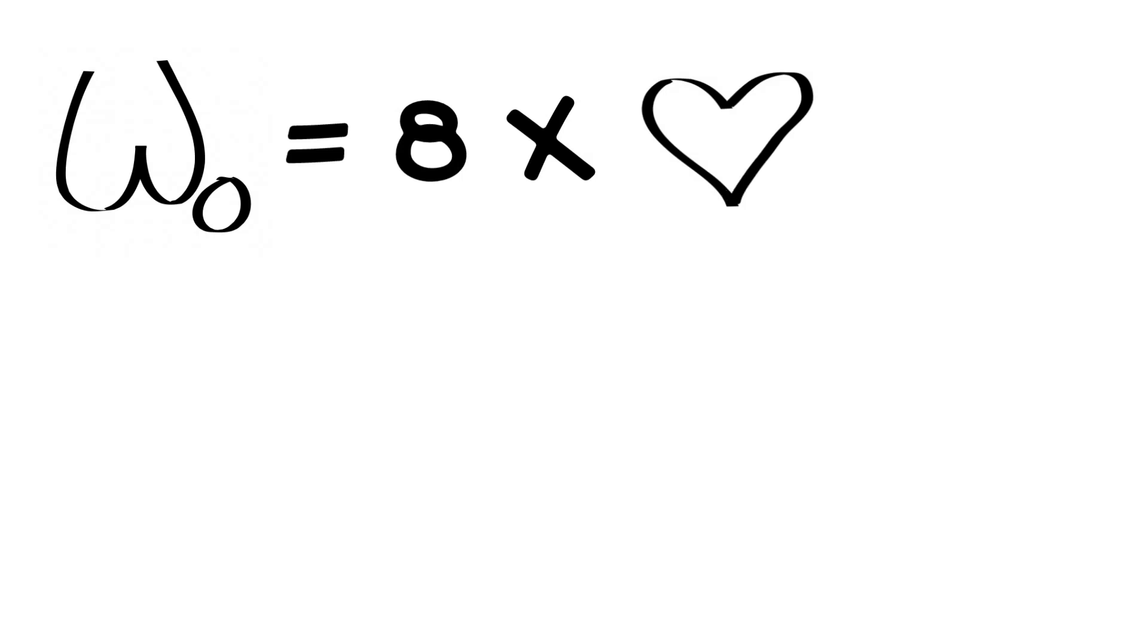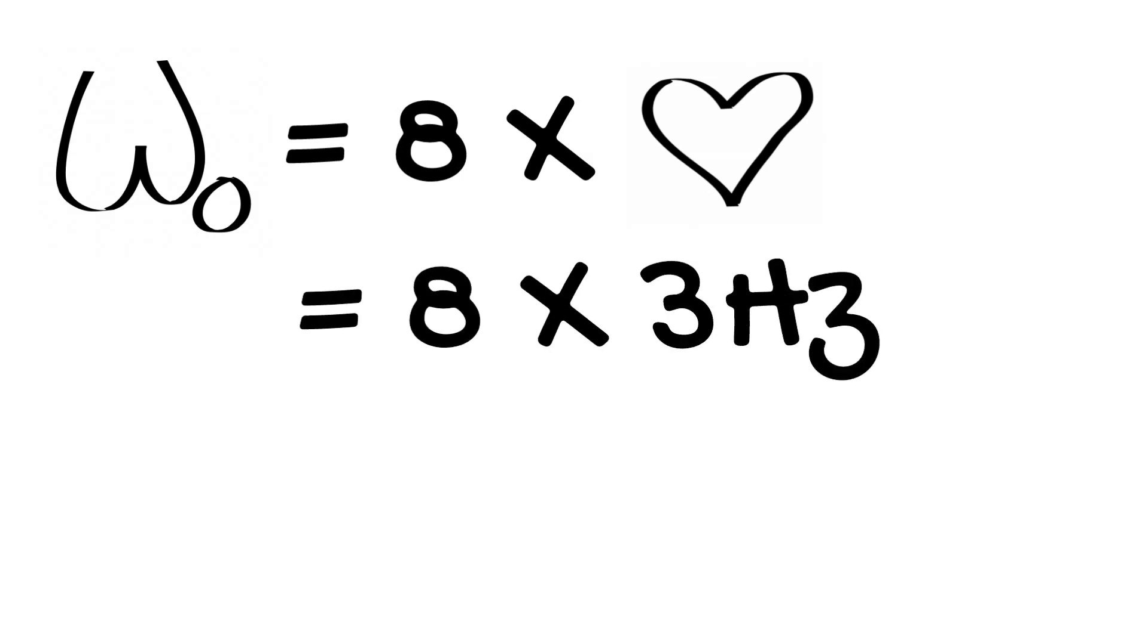If the fastest heart rate we are measuring is 180 beats per minute, that is 3 hertz. If we multiply that by 8, the frequency of our system has to be at least as high as 24 hertz.